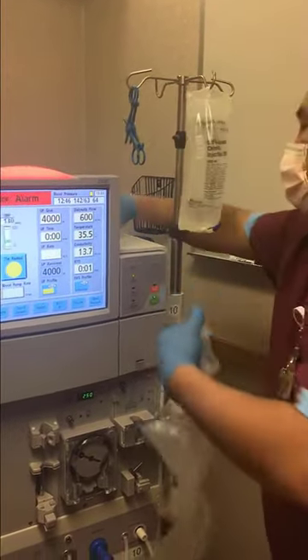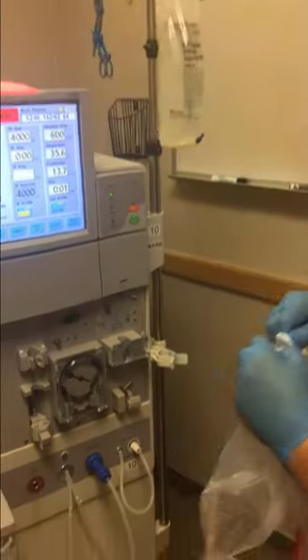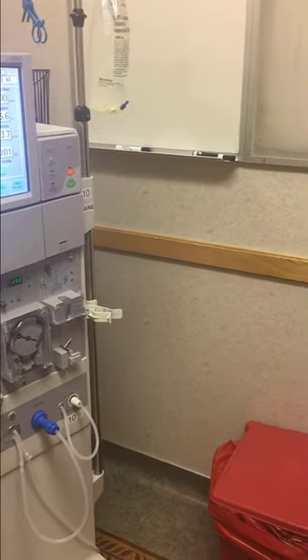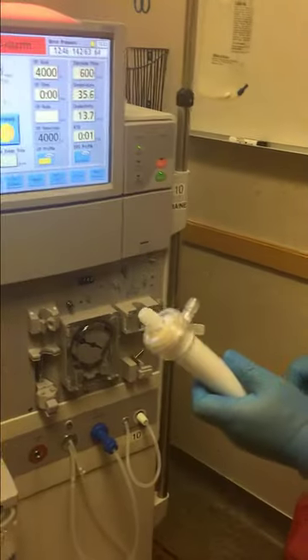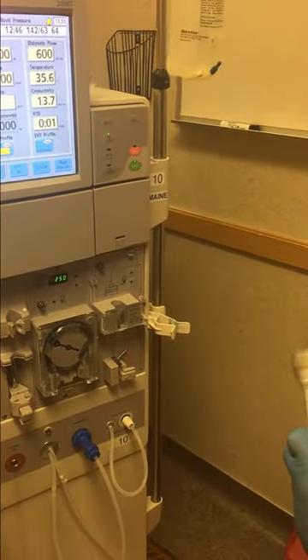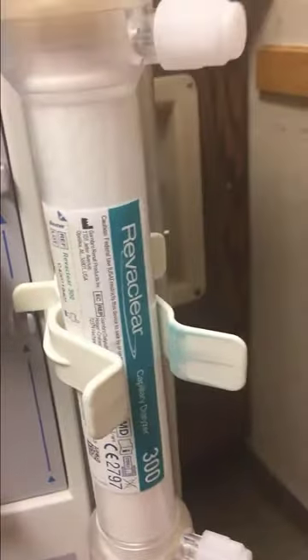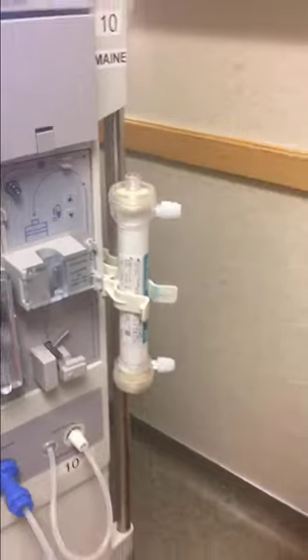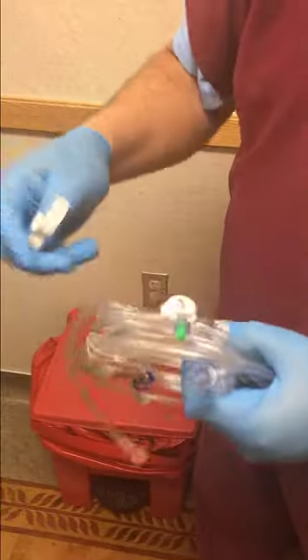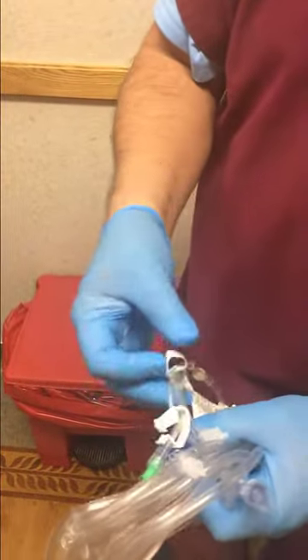So the first thing you're going to do is hang your saline, and you're going to make sure there's no defects with the saline, that the bag is intact, and that the expiration is good. And go ahead and take your dialyzer out and place your caps on the side ports. And then the next thing you're going to do is open up your tubing. And depending on how you wish to do this, you can clamp all the small clamps at this point if you wish. Or you can do it as you work through the process of priming.